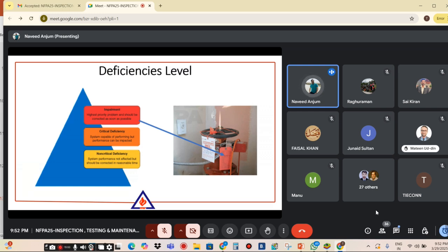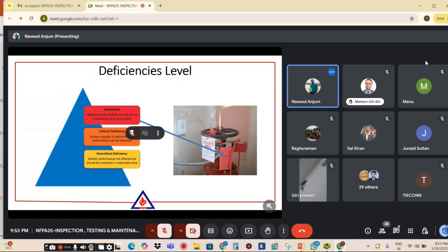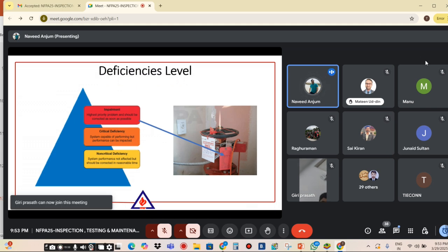NFPA 25 mentions 3 levels of deficiencies: impairment, critical deficiency, and non-critical deficiency. We can also use 3 types of tags, yellow, orange, and red, for these deficiencies. Firstly, we will discuss non-critical deficiencies. These are deficiencies in which system performance is not affected but should be corrected in a reasonable time. Like if our valve is a little bit damaged, but our system is working okay, we will correct it after some time. It's not urgent, it's not a critical deficiency, but we have to correct it.